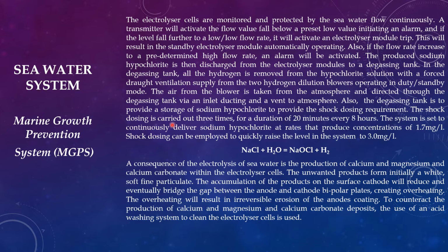Also, the degassing tank provides storage of sodium hypochlorite to meet the shock dosing requirement. The shock dosing is carried out 3 times a day for a duration of 20 minutes. Every 8 hours it is dosed. The system is set to continuously deliver sodium hypochlorite at a concentration of 1.7 milligram per liter. Shock dosing can be employed to quickly raise the level in the system to 3 milligram per liter.